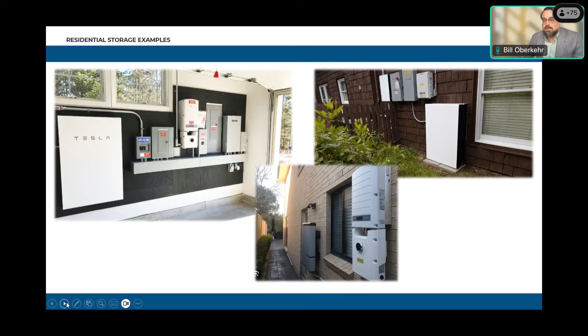Per the residential code, residential systems are only allowed up to 40 kilowatt hours within a utility closet and storage or utility spaces. And that again has to be completely enclosed by a fire resistance rated wall, including the ceiling. We can go up to 80 kilowatt hours in total aggregate capacity for a residential system on an attached or detached garage or accessory structure on the exterior wall. But in that case, you need a fire resistance rated wall that the battery is mounted on, between the battery and the living or dwelling space. And then for outdoor ground mount, we can also go up to 80 kilowatt hours aggregate capacity for residential systems.